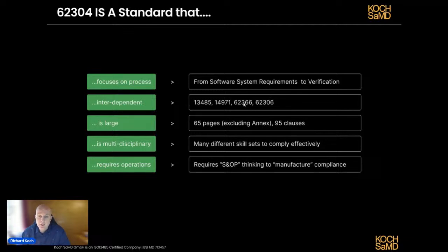However, the process is also interdependent on other processes. So it has to comply to 13485, 14971, 62366, 62306. And again, depending on the complexity of your product and your country regulations, there are a lot more. So it is not a standalone process.